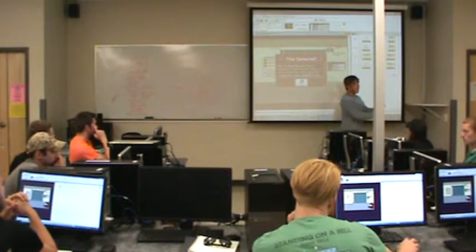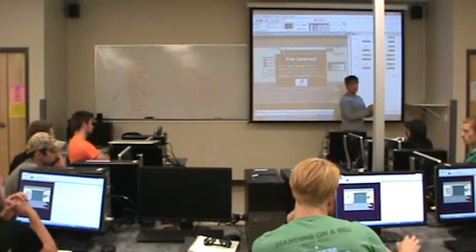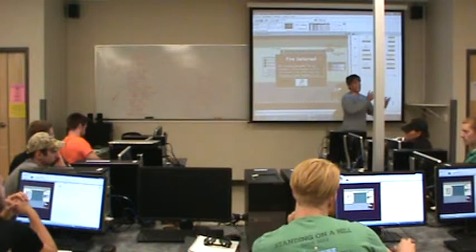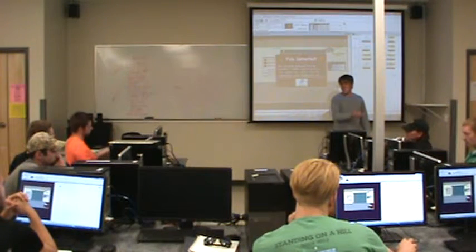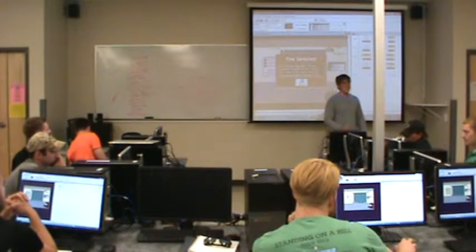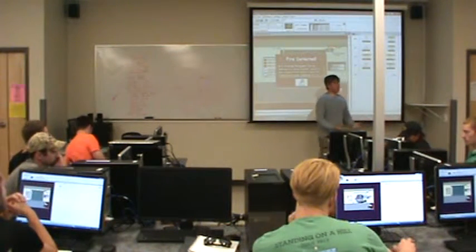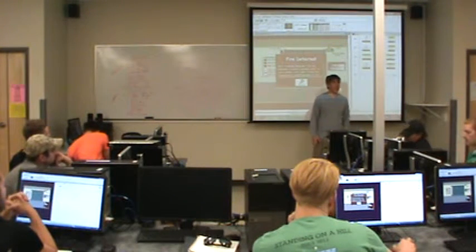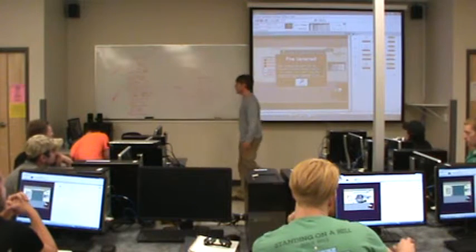operator, right, hit the down button at the same time as up had been pressed, because they panicked and they realized that, oh, it shouldn't be moving up, I needed to move down. They didn't think to hit stop first, we have the program stop it anyway. Okay? They just hit down. What happened was the PLC said, okay, I'll try to move the door up and down at the same time. It energized the up and down windings and got a fire.